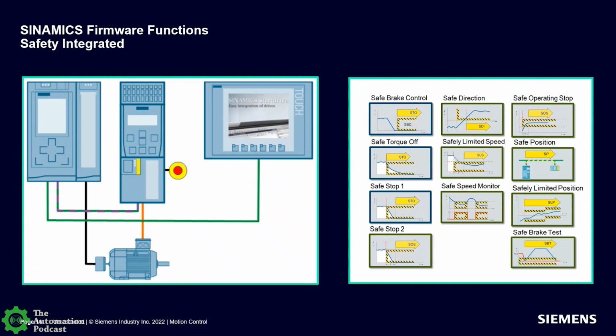Maybe you just want to do an STO and hardwire it in — we offer that across the range of drives, where you can do a simple two-channel hardwired STO. But when you want to move into doing this over ProfiSafe and tie it to a fail-safe PLC, that's when we move into more capability, like a Sinamics G drive standard version versus the fail-safe version. Or if you move into the Sinamics S-type system drives, you'll have basic drives-based safety integrated functions built in. When you want more advanced applications, we can add that with a safety license to enable those functions.